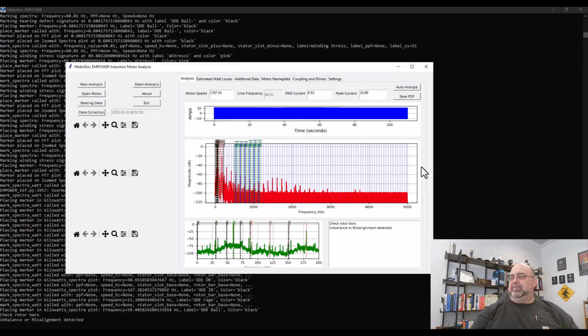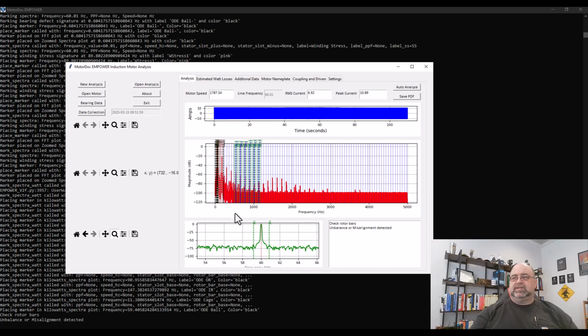Okay, so let's see. Unbalance or misalignment, that makes sense. Rotor bars, let's take a quick look and see what it selected at speed. So relatively high speed, let's see if we got the rotor bars. Yeah, tiny little peaks, so with adjustment still, that's definitely going to be casting voids.